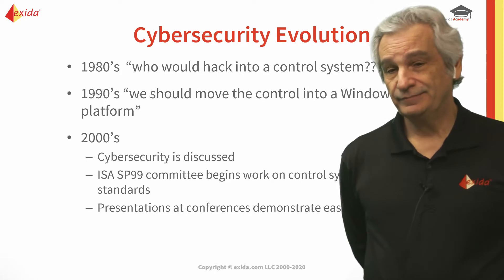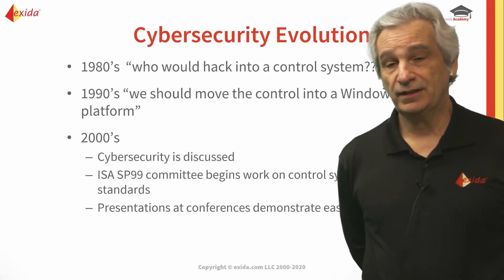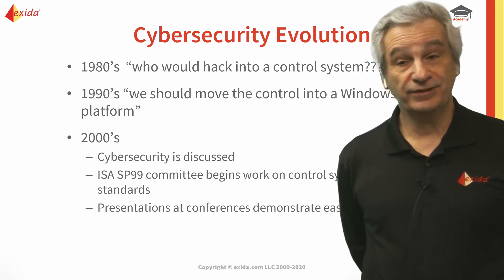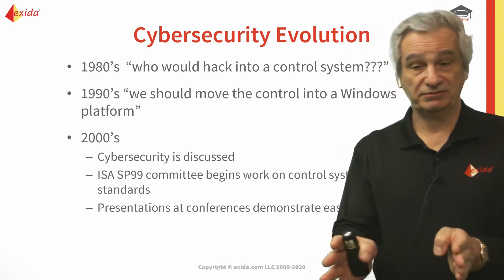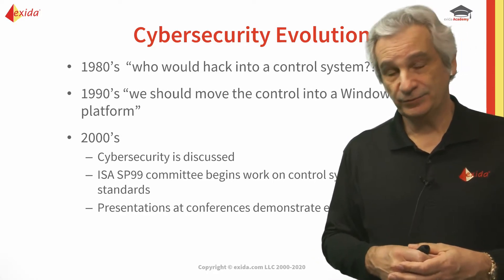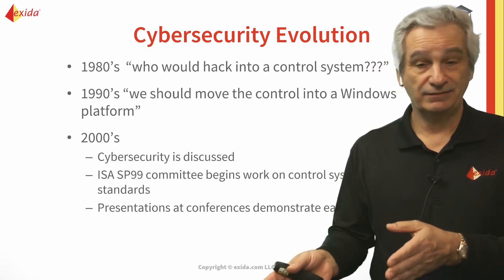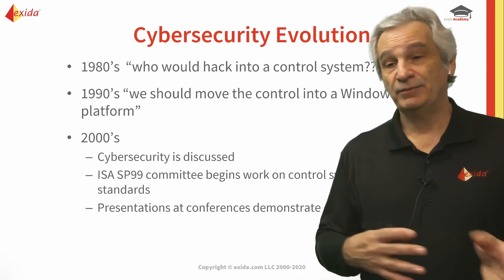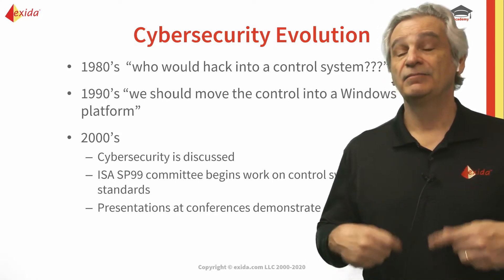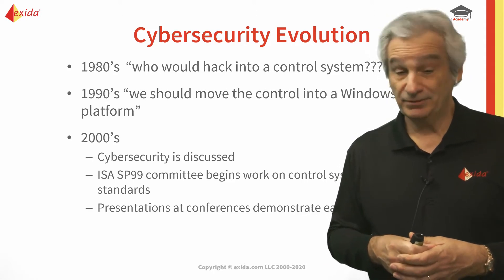So what do we do when we had a fault to find? Well, that was always a challenge. What we ended up doing was putting in what were known as backdoors. I could go up to some of our equipment running in automatic, plug into the RS232 port on the front with a handheld RS232 ASCII keypad, put in a sequence of ASCII keys, and it would take the controller out of automatic and allow me to look at the serial registers and IO memory — I could manipulate and do things. When finished, I could put through a series of ASCII keys to put it back into automatic. I could still remember those codes now, and I'm sure some of those systems are still out there and probably still have these backdoors in.